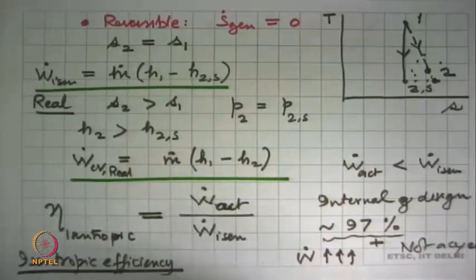And the generator coupled to it, it takes mechanical power in, mechanical power out. And so we can define generator efficiency, and that's not an isentropic efficiency in this case, but it will be an ideal case that work output divided by work input. We are not comparing it with the ideal case, but big generators, this efficiency is of the order of 99.5, 99.7%. The remaining is lost as magnetic losses, heat losses, I2R losses, but big generators are very, very efficient. So this is one part of the story of what happens in a work producing device. How efficient can we get? Hydro turbines efficiency will be somewhat lower, 90%, 95%, but still scope to improve it.